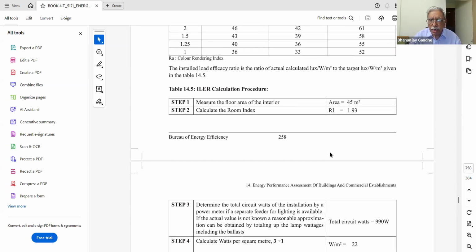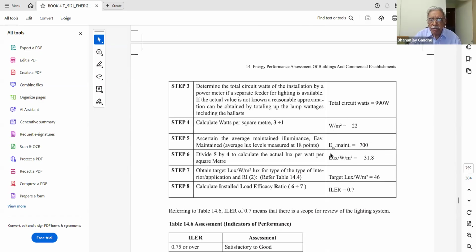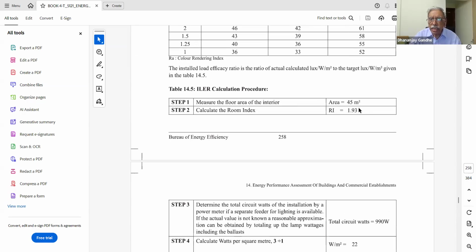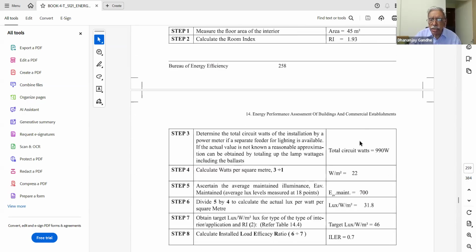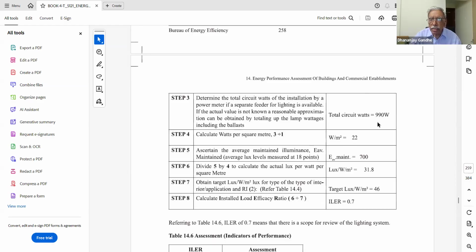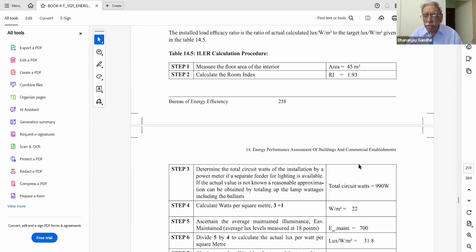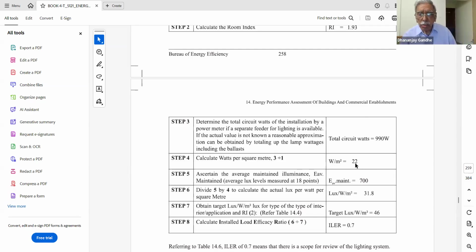So watts per m square is the lighting density. That works out to 990. That's the total wattage divided by the area. So watts per m square density is 990 by 45, which is equal to 22. So this figure works out to 22. These are the stepwise calculations.